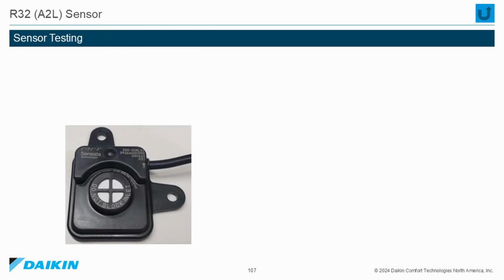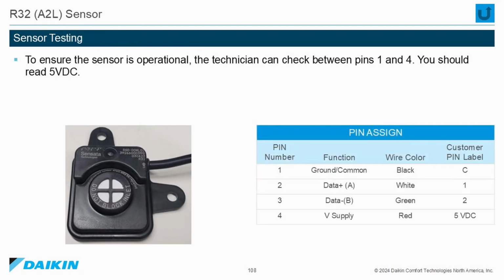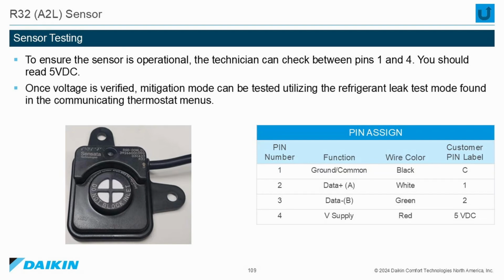Sensor testing. To ensure that the sensor is operational, the technician can check between pins 1 and 4. You should read 5 volts DC. Once the voltage is verified, mitigation mode can be tested utilizing the refrigerant leak test mode found in the communicating thermostat menus.